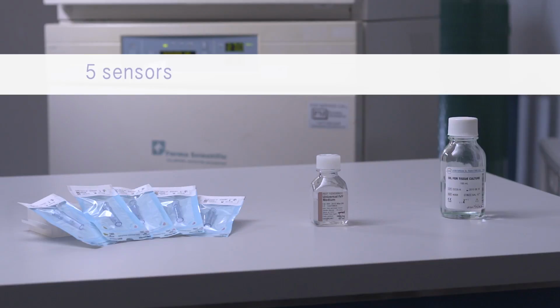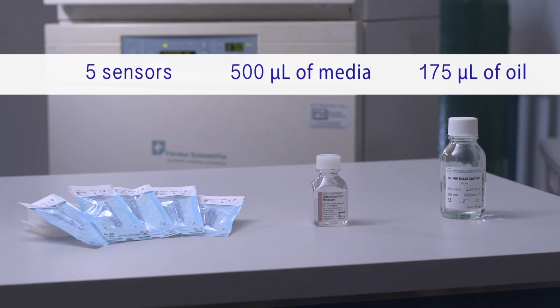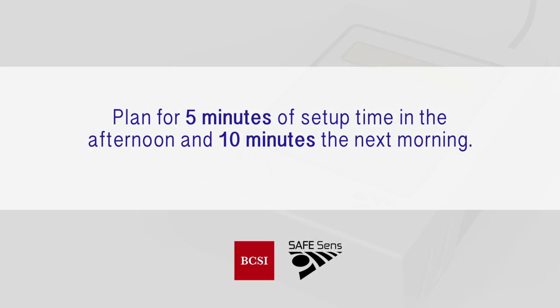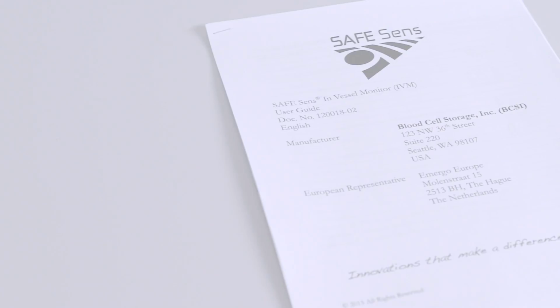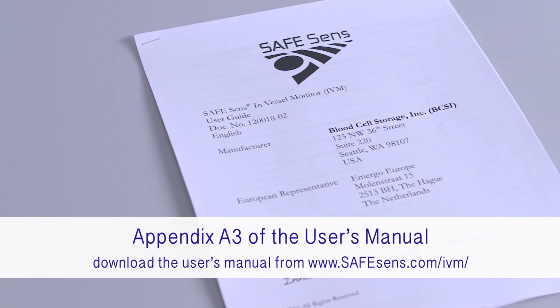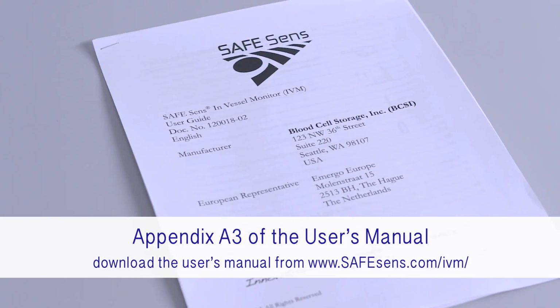Once you have your SAFE Sens installed in your incubator, gather your required materials. You will need 5 sensors, 500 microliters of media, and 175 microliters of oil. Plan for 5 minutes of setup time in the afternoon and 10 minutes the next morning to perform the pH readings. If you want to follow along, the protocol is in Appendix A3 of the user's manual.